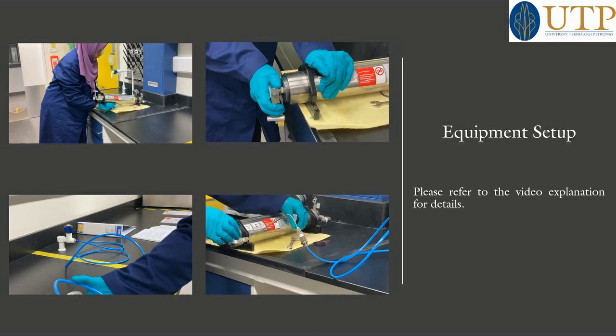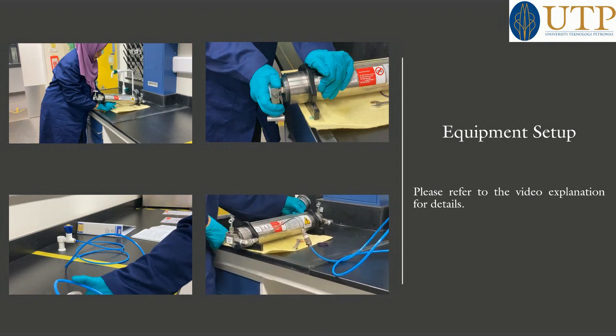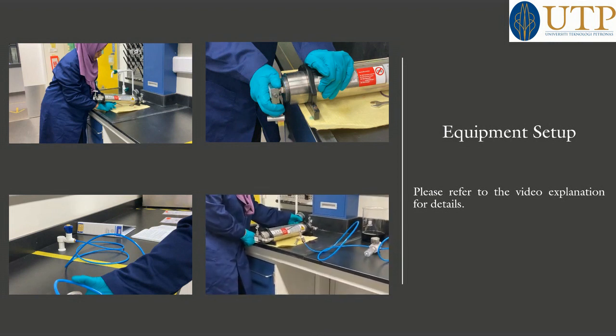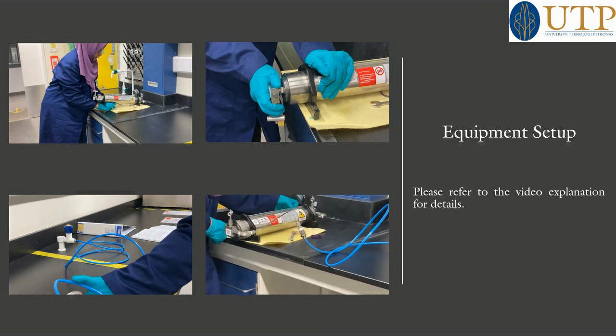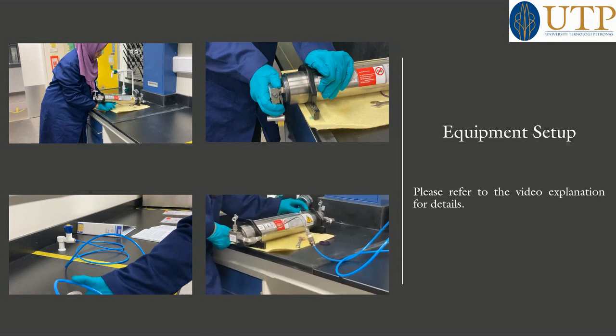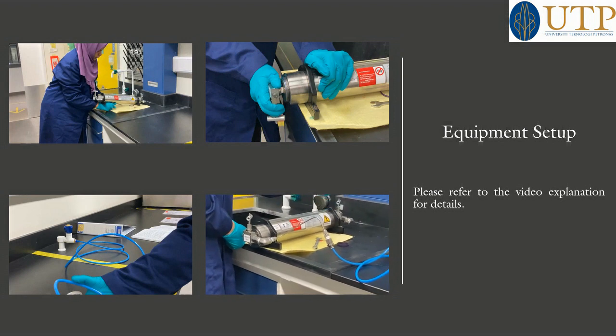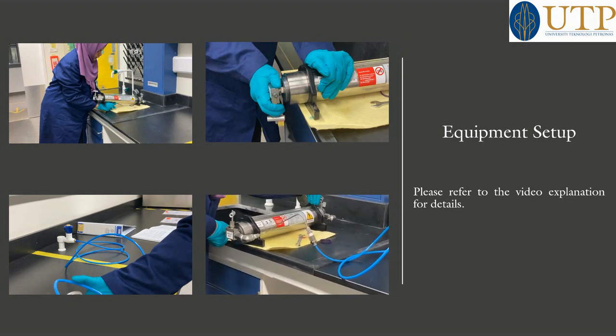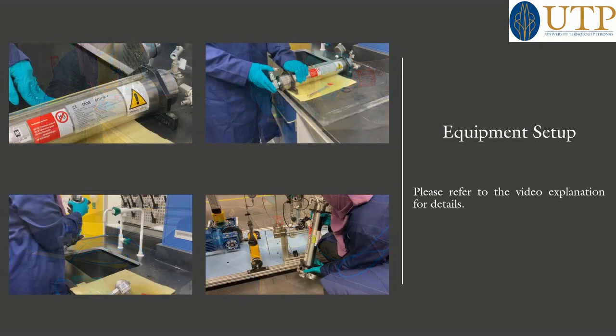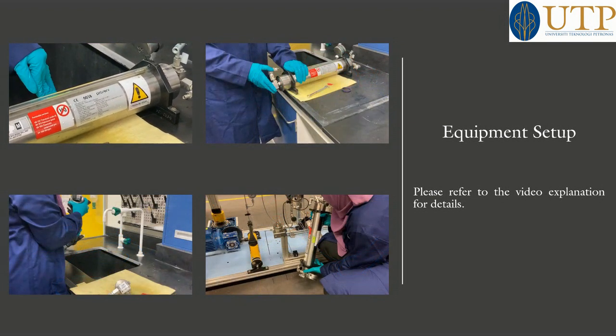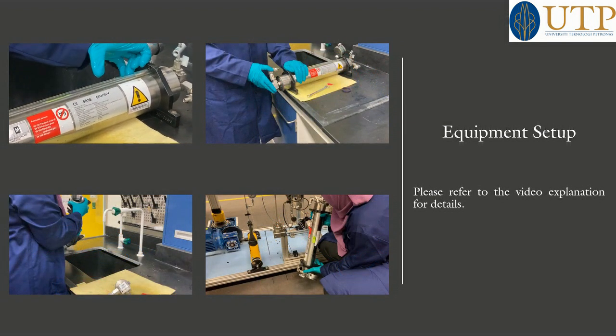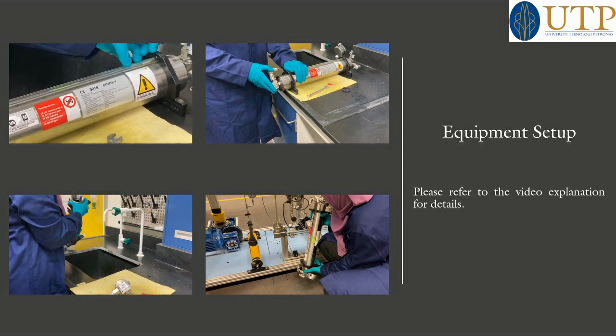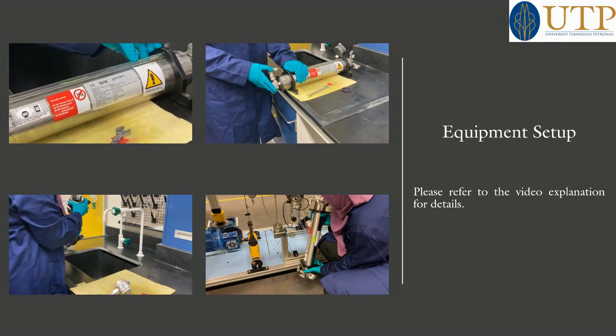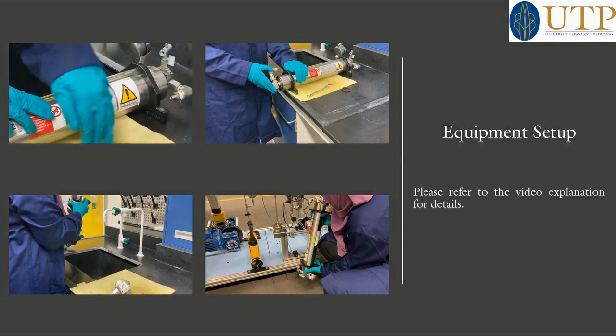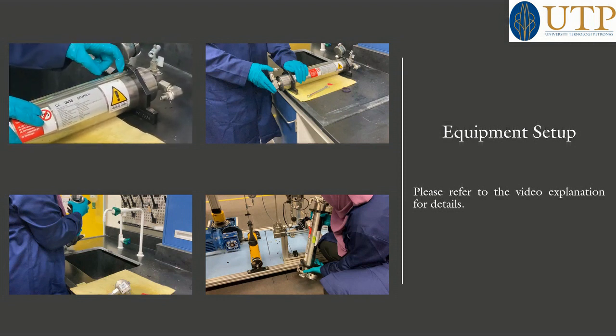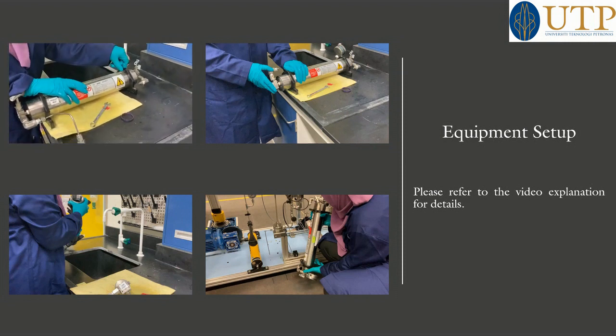Okay, so you can see here the magnet is now in this place. It was here, now it's here. That means there is no water left inside the accumulator. So previously the magnet was here. When we give this pressure, this airflow, it flushes all my water, and now you can see the magnet is here. That means there is no water left inside the accumulator.